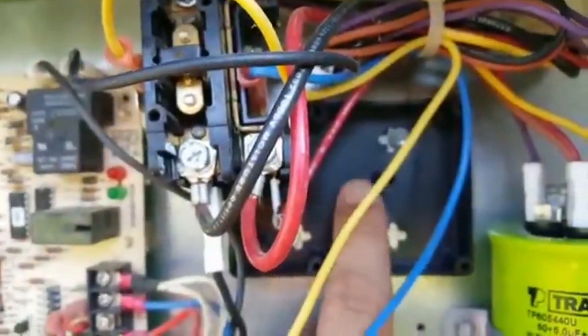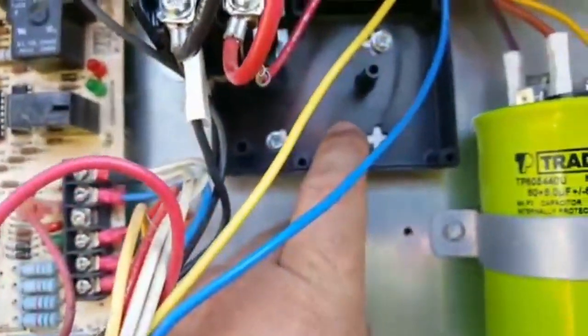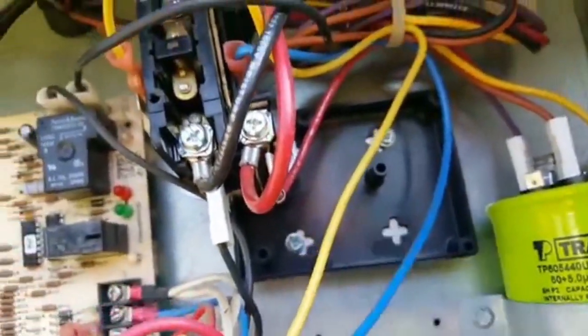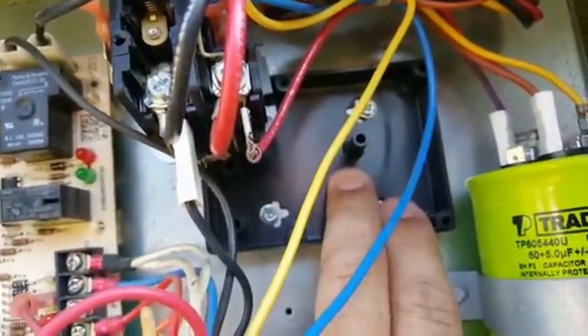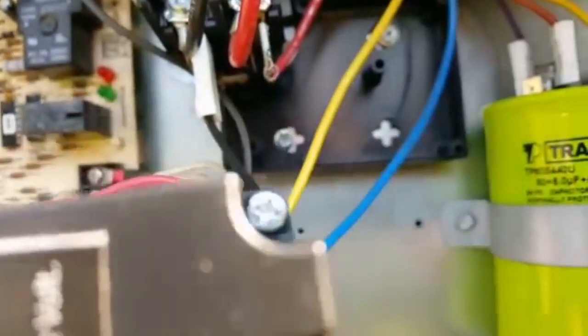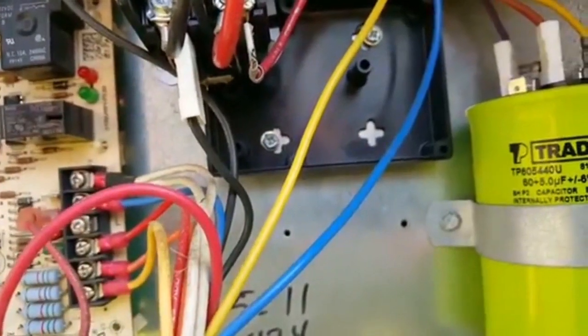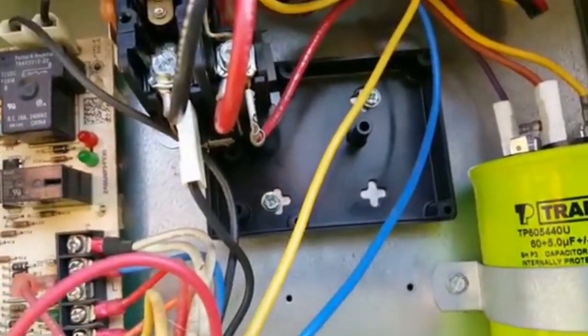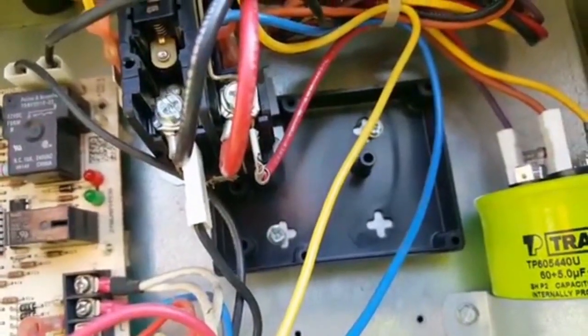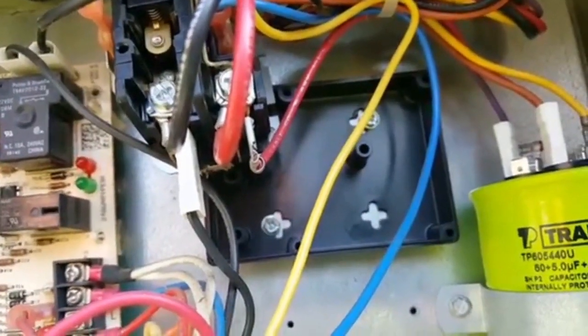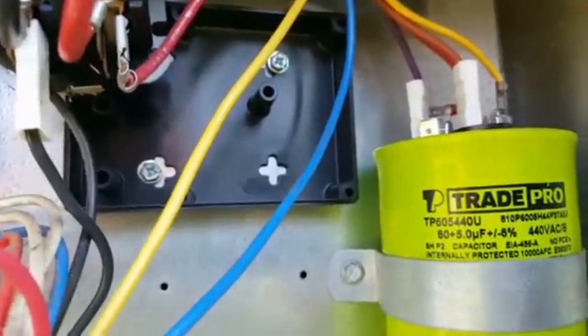Okay guys, I have the base mounted right here for the SureSwitch. You can see it. I've got the contactor still in place. I just pull it out of the way, take wires off one by one and put them on the SureSwitch. And then the top of it will mount onto that with these screws right here. And then we can go ahead and get this thing fired up, and I can hit the test button and let it run, so we don't have to wait on the delay. And that'll test both the capacitor and the SureSwitch.